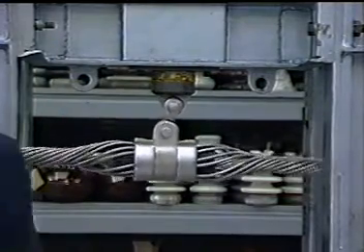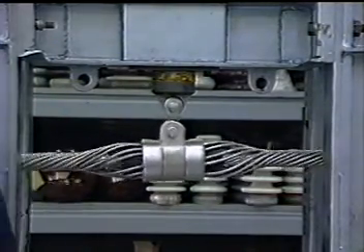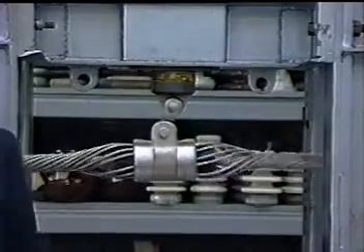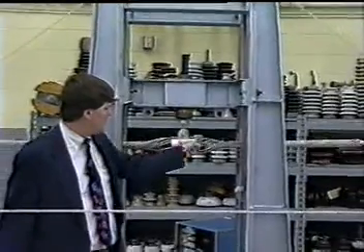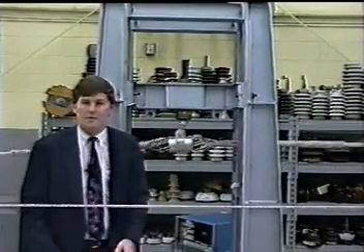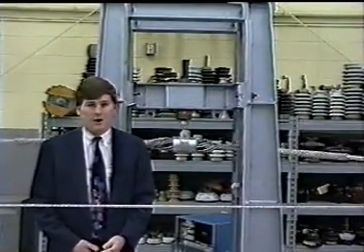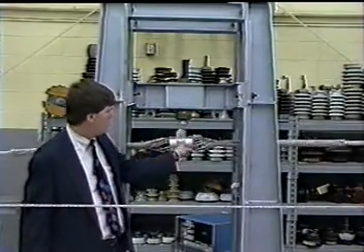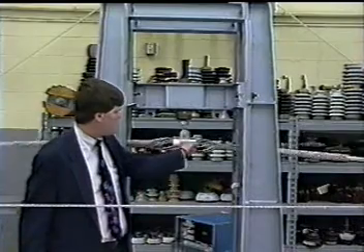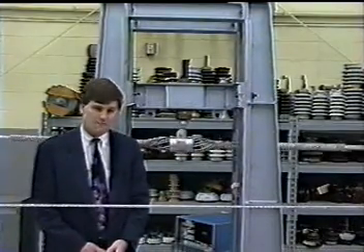Now, as the cable is going up and down and galloping, we are having high bending stress due to the galloping motion, and also you will notice a longitudinal stress, and this is typical of galloping. In aeolian vibration, you only have stress due to bending. Here we have stress due to bending, and we have stress due to a longitudinal axial loading.